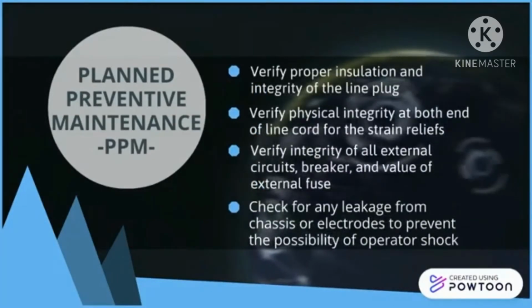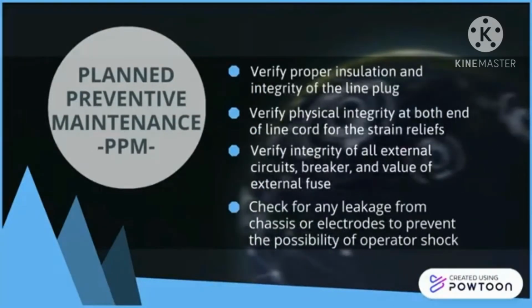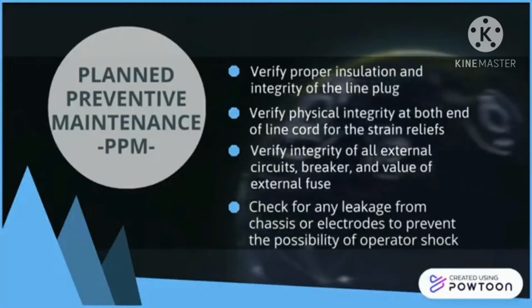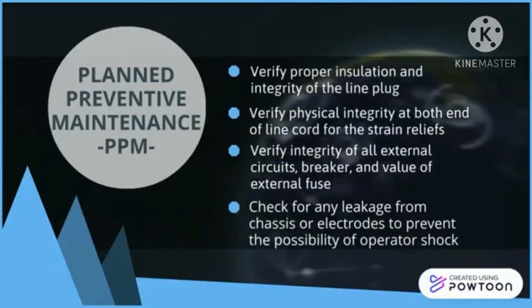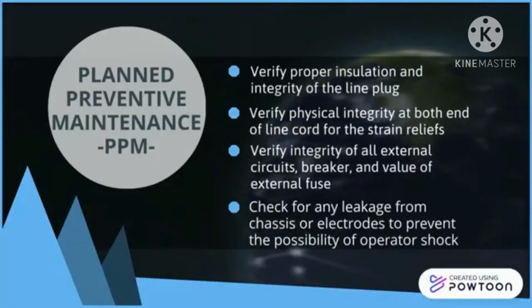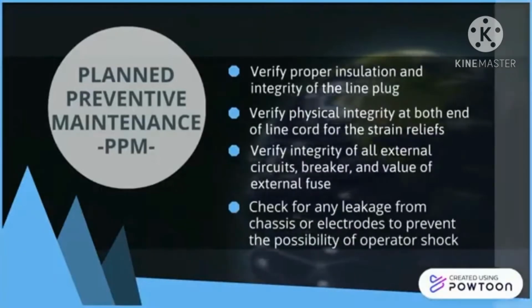Verify proper insulation and integrity of the line plug. Verify physical integrity at both ends of the line cord for the strain reliefs. Verify integrity of all external circuit, breaker, and value of external fuse. Check for any leakage from chassis or electrode to prevent the possibility of operator shock.